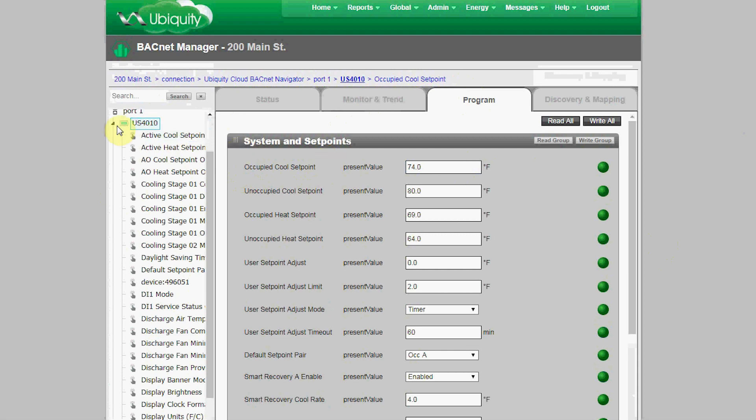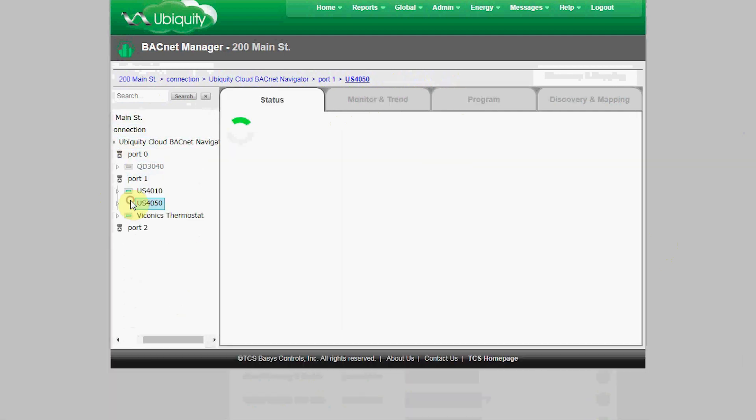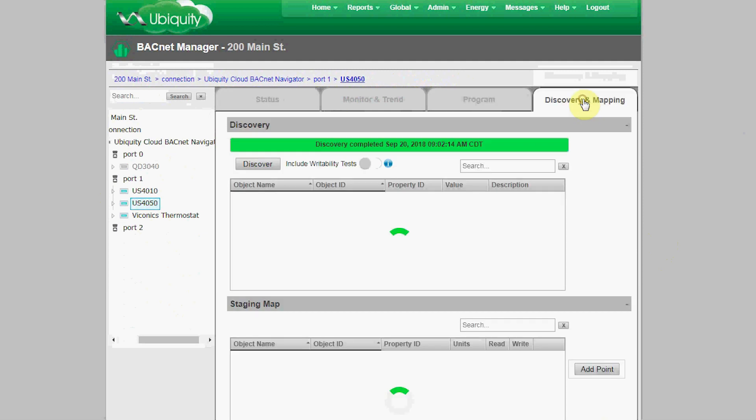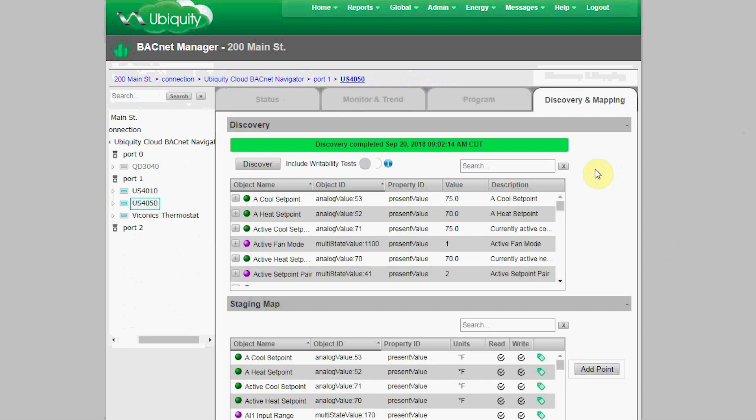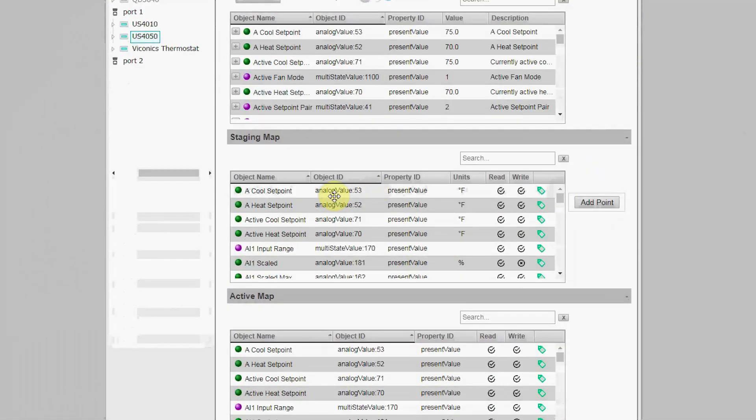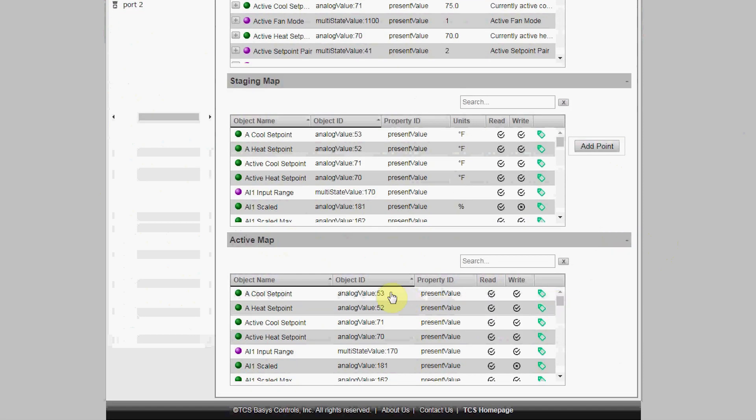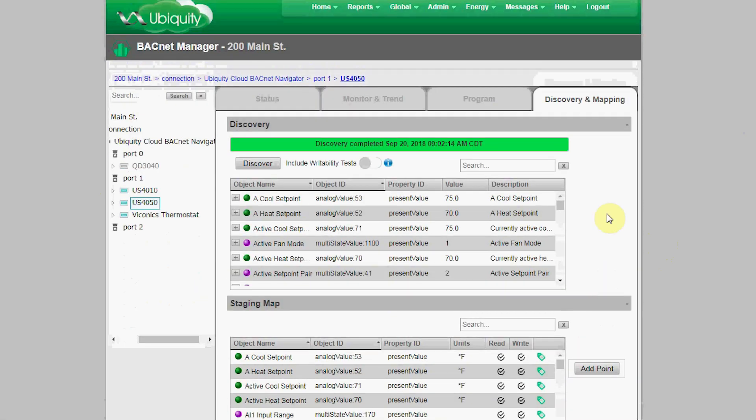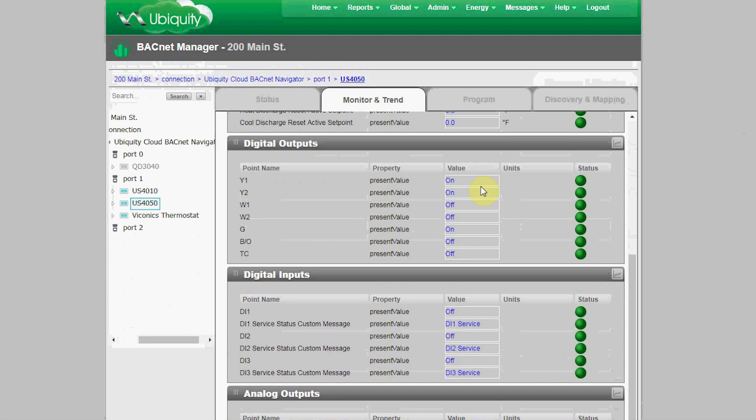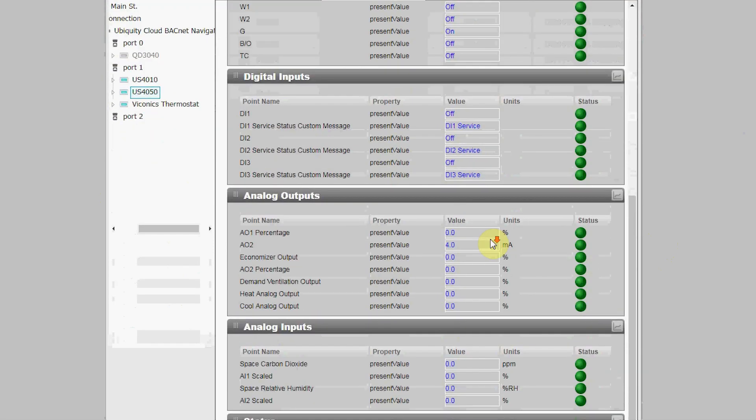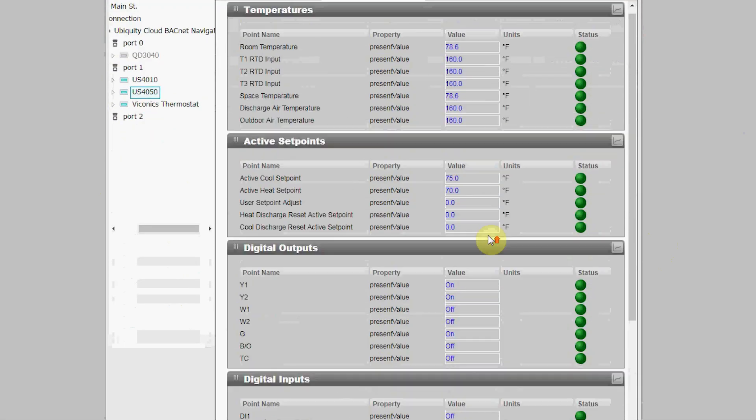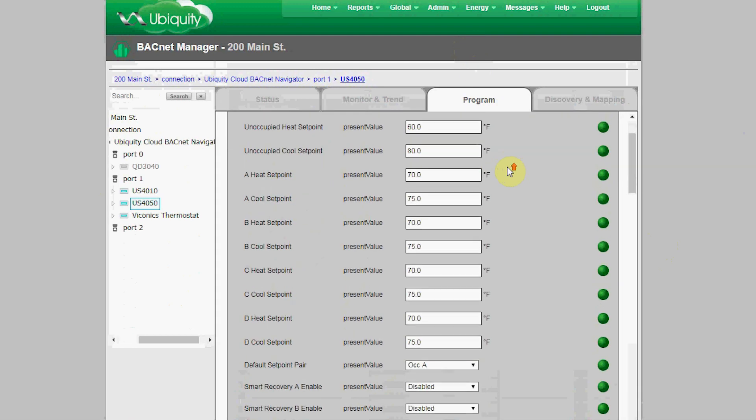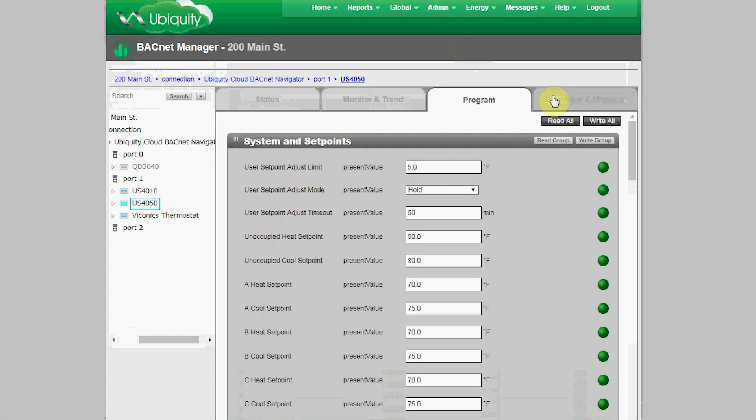When a TCS Ubiquistat is added to a network, like the US 4050 model we have here, we have an auto-detect feature. So the QD 3040 edge device auto-detects the device and pushes the discovery automatically to the BACnet Manager. The BACnet Manager then automatically, based on the device model number—in this case the US 4050—will automatically map objects to the staging and also the active map, along with associated tags. Those tags then create default monitoring and programming and trending pages for the device, so a user with read-write access can use the device immediately.